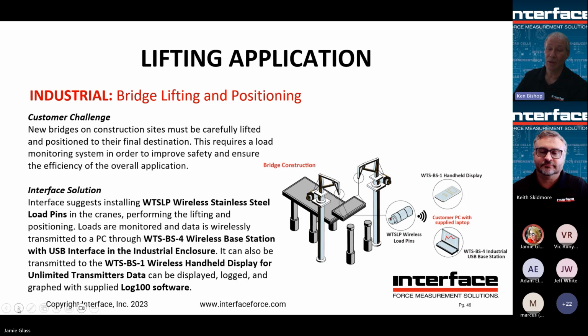So again, the load pins were custom fitted to match the crane's size and strength and loads being lifted. They're the right IP level, so more than likely an IP67 protection. The wireless load pin can transmit up to 600 meters. So depending on where the recordings want to be taking place, where power exists, the power of the PC, as long as it's within the 600 meters.